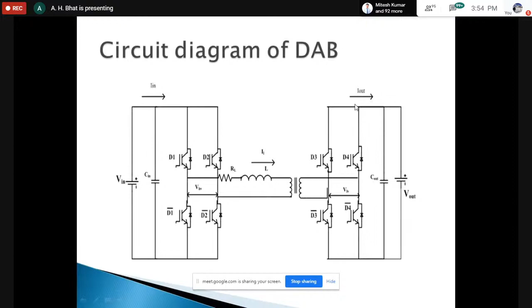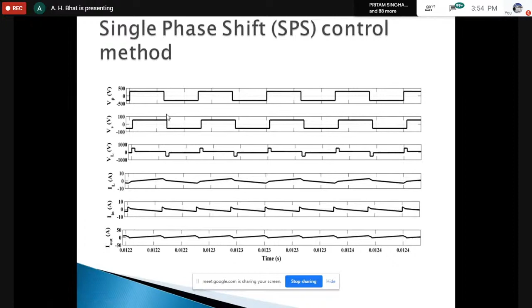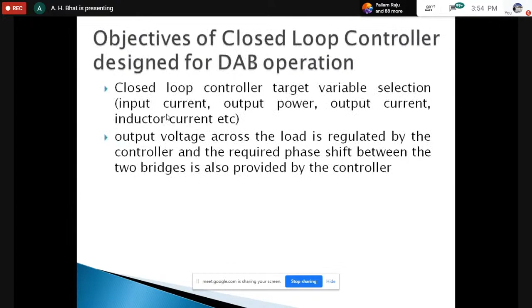Now, it is this primary side current and secondary side current which will tell you whether power is flowing from high voltage bus to low voltage bus or vice versa. Let me tell you that this phase shift, since the primary voltage is leading the secondary voltage, in this case power will flow from high voltage DC bus, that is primary side, to low voltage DC bus, that is secondary side.